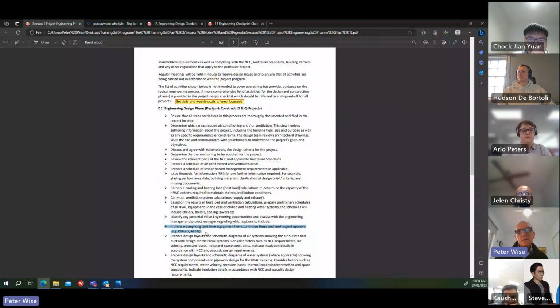If there's any long lead time equipment, prioritize these and seek urgent approval. Chillers and air handling units sometimes have a long lead time. Most air handling units these days are made overseas. There are still some manufacturers in Australia, but unfortunately the pricing is quite high, so they tend to come from overseas and can take 12 to 16 weeks delivery, depending on the complexity of the unit. Be aware of those things.